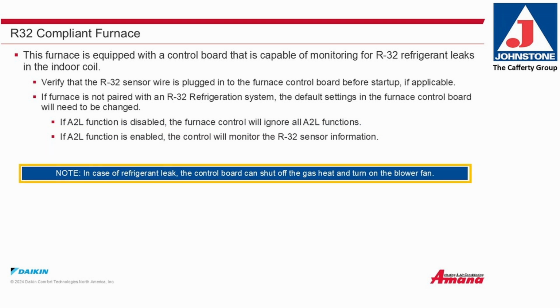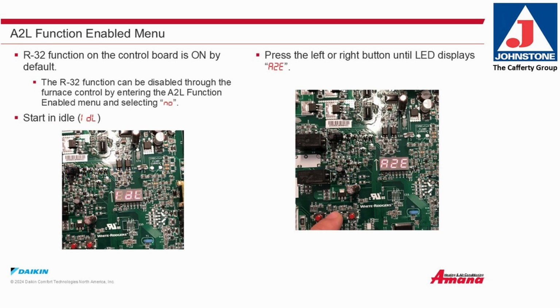In the case of a refrigerant leak, the furnace control board can shut off the gas heat and turn on the blower fan to mitigate the R32. The A2L function enabled menu. R32 function on the control board is on by default. The R32 function can be disabled through the furnace control by entering the A2L function enabled menu and selecting No.